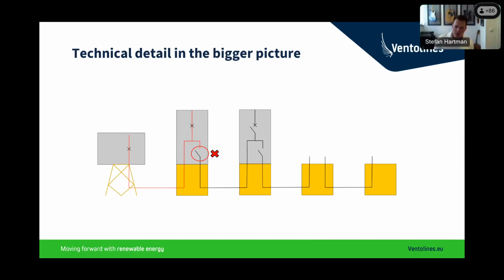On a 33 kV turbine, this was all fine. You could do this under voltage. However, moving to 66 kV turbines, we found out that we cannot do that anymore due to larger inrush currents, and you would get flashovers in your switchgear. Not good. So we need to do something different here if we want to energize the second inter-array cable. Next slide, please. We first need to open the circuit breaker of the switchgear towards the turbine. That means that we interrupt the trial run.